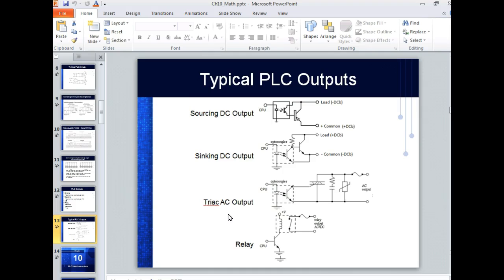On the output side, you have different module types: a transistor output, a sourcing DC module, a sinking DC module, and an AC module using a triac. Triacs are used as AC switches — they're primarily AC switching devices. If you've ever heard of a solid state relay, it usually uses a triac. If you have motion detectors at your house that turn on a light, odds are they use a triac — it's a solid state switch.